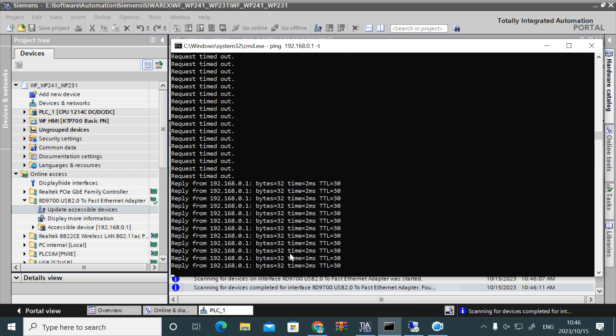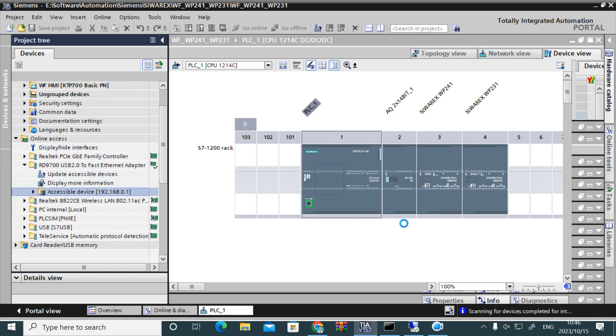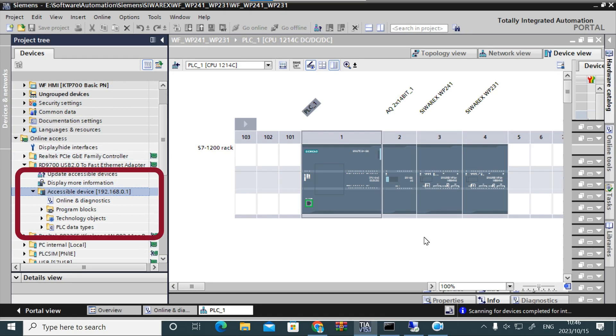Now going back to the accessible device and expanding it, you can see it has more functions available — online diagnosis, program blocks, technology objects, PLC data types — because it is now working with Ethernet TCP/IP. Earlier it was only working with Ethernet ISO, which is why it was showing fewer functions, only online diagnosis.